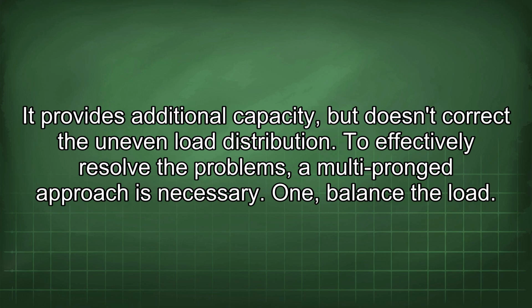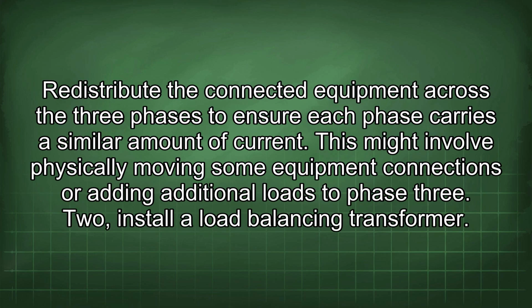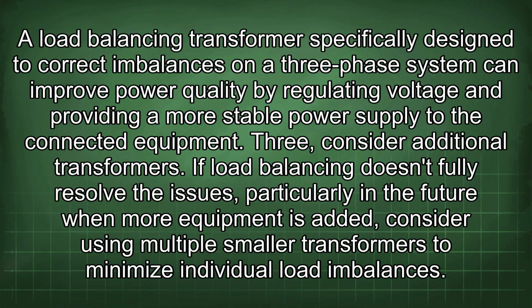1. Balance the load. Redistribute the connected equipment across the three phases to ensure each phase carries a similar amount of current. This might involve physically moving some equipment connections or adding additional loads to phase 3. 2. Install a load balancing transformer. A load balancing transformer specifically designed to correct imbalances on a three-phase system can improve power quality by regulating voltage and providing a more stable power supply to the connected equipment.